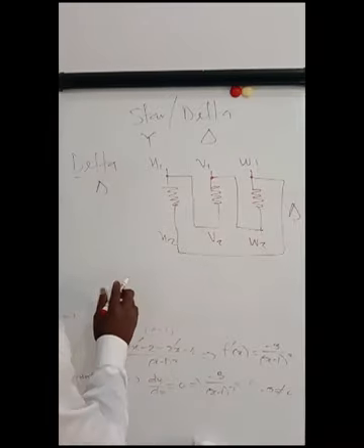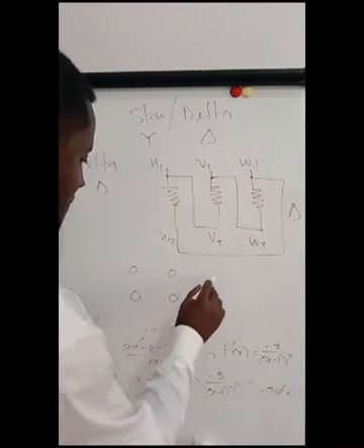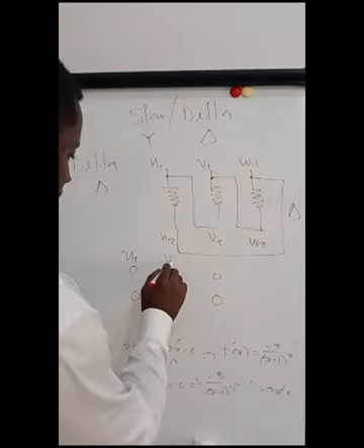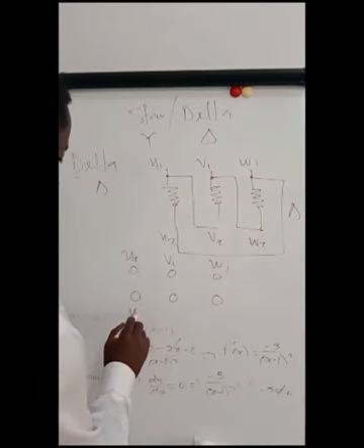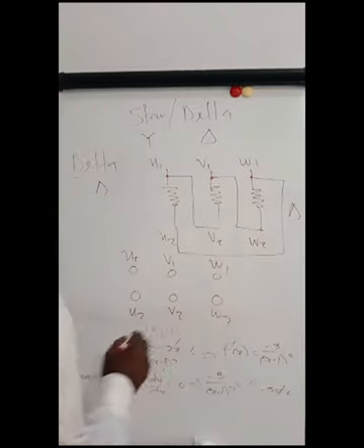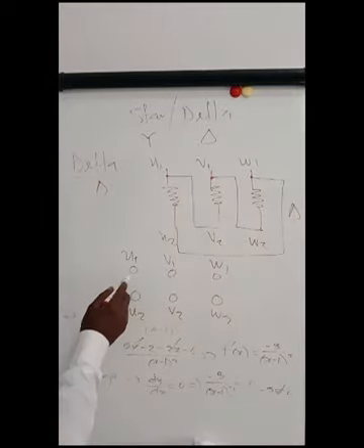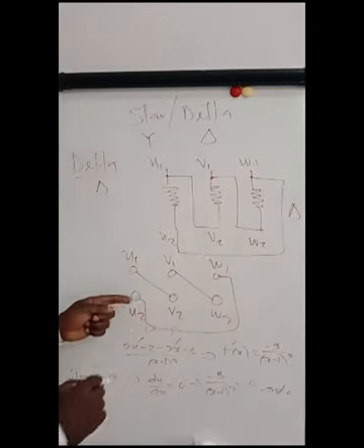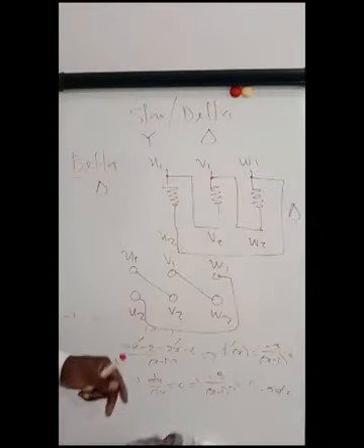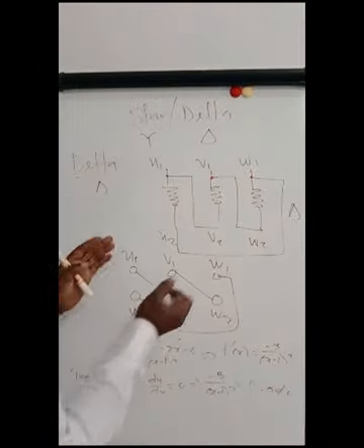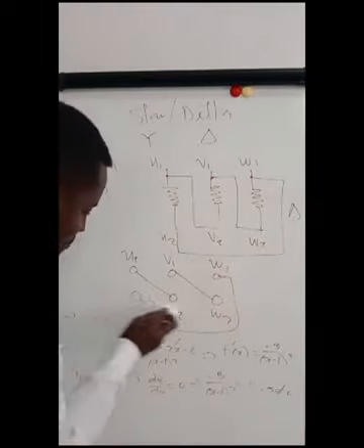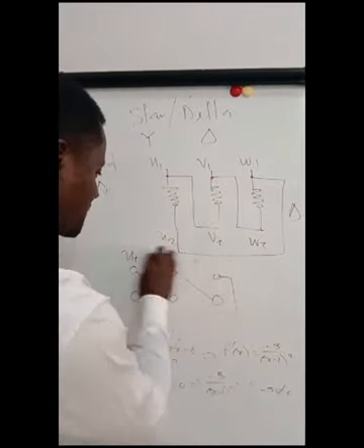If you look at your electric motor now, we have our terminal board as such, which will be U1, V1, and W1, and here will be U2, V2, and W2. To connect this in star, all these are going to be connected together. As you can see, these will move and connect to this winding. But in the electric motor, it is done in such a way that we can achieve both star and delta without having all these connections as such.